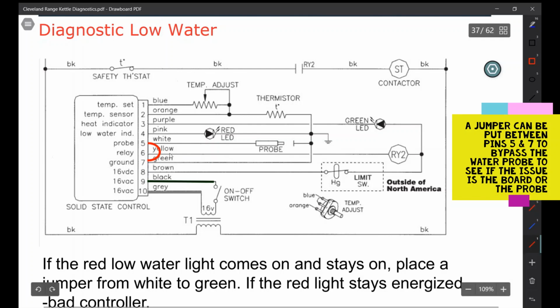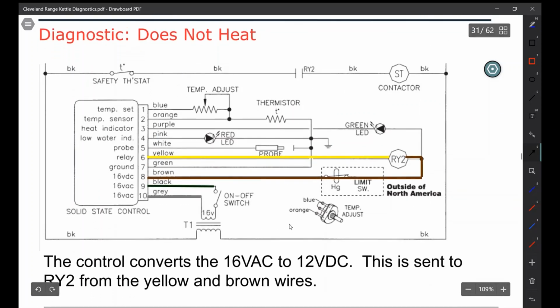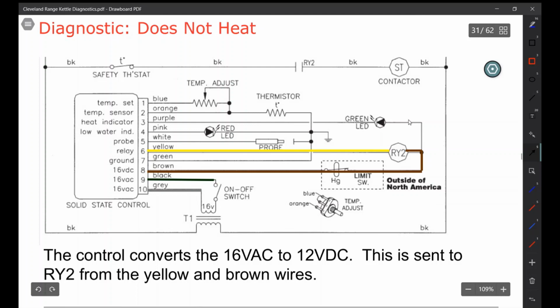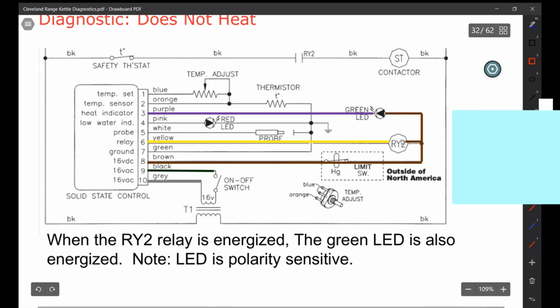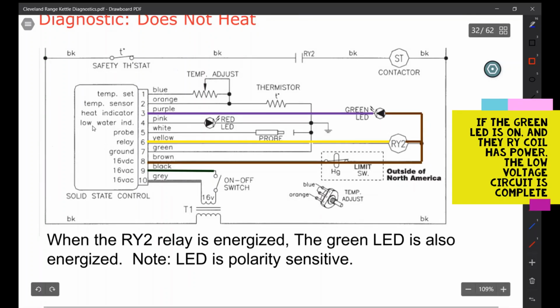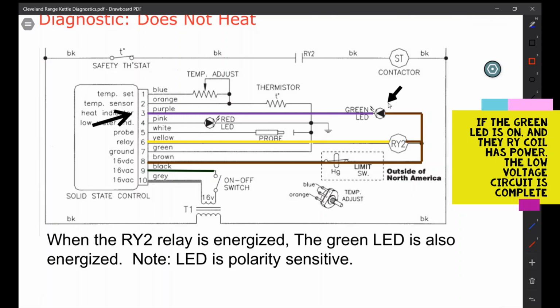It's just really hard to put a jumper in here. So generally I'll take off the white wire and ground it to the chassis. So off of pins 6 and 8, we're going to send power to our RY2 relay. Power is also going to be sent to pin 3 for the green LED. So if the green LED is on, most likely the RY2 relay coil has power. And this is very important for troubleshooting because if you have that green LED on, you probably don't have to test anything on this low voltage circuit.